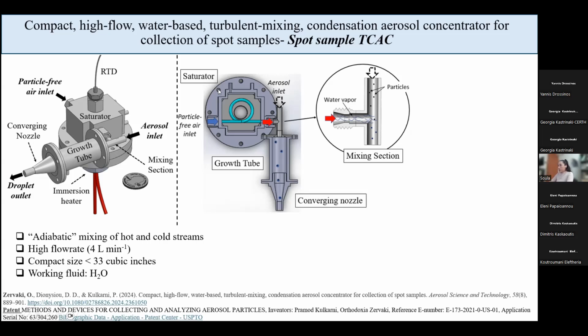First, we have the saturator. The saturator is basically a water container that has an immersion heater at the bottom and a temperature sensor at the top. Inside the water container, we have a Nafion tube, that is a membrane that is only permeable to water molecules. At the entrance, we have particle-free air coming in at room temperature, and at the exit, we have a water vapor saturated flow at the same temperature as the water that is being heated inside the container.